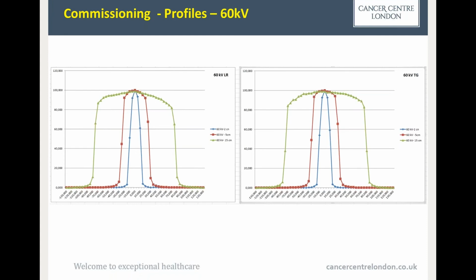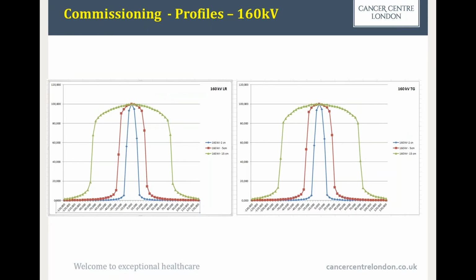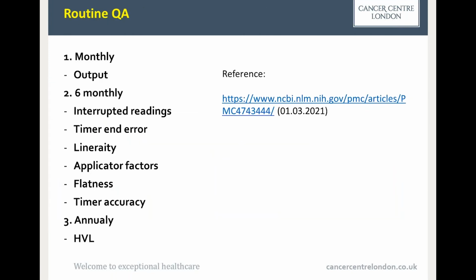If we go ahead, we have measured our profile for 60 kV, and you can see this heel effect is not so strong, but is visible. But we can say that we are still happy with this coverage of field, but of course it will be significantly better for 160 kV because of higher transmission. And we just checked this coverage, and whether we can say that we have uniform profiles. And really, that is everything we have done in terms of measurement and commissioning.